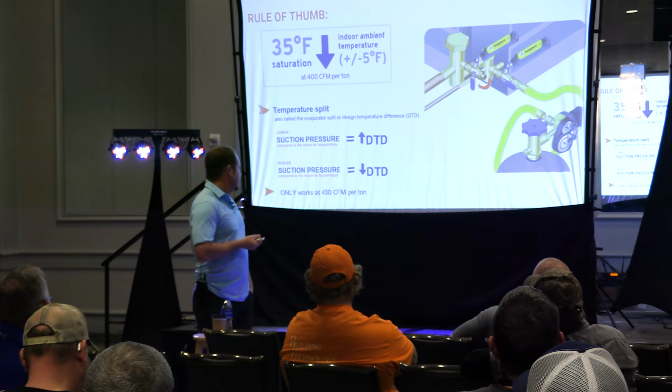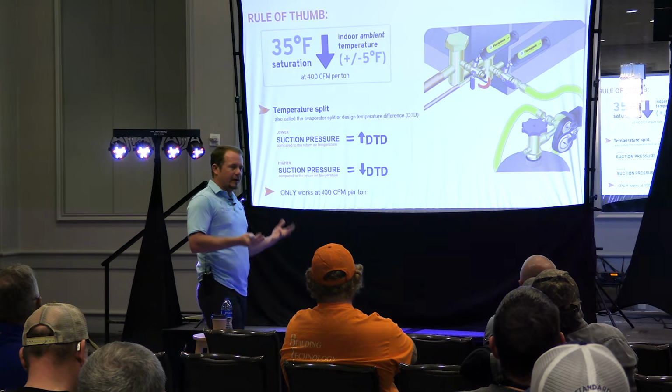But then we start to ask the question, and we ask very quickly, well, what are the exceptions? Well, we say right here, this only works at 400 CFM per ton typically. Here we design for 350, and then we have higher relative humidity, so it's going to be a little outside of that in most cases. But you pick up pretty quick.